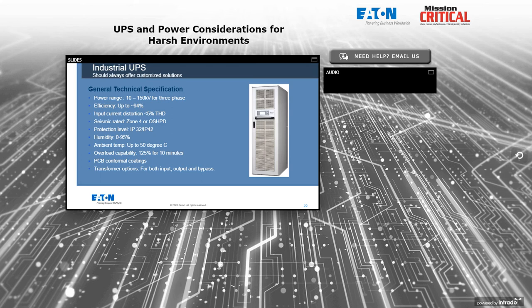We've talked about conformal coating for the PCB. Maybe not every PCB is conformal coated, depends on the client's requirements. Some things like surge suppression devices and that type of thing may not have a conformal coating, but the control and the power circuit PCBs would typically be conformal coated. And then for clients that need isolation transformers on the input or the output or both, much more common to see that requirement here in industrial UPSs.